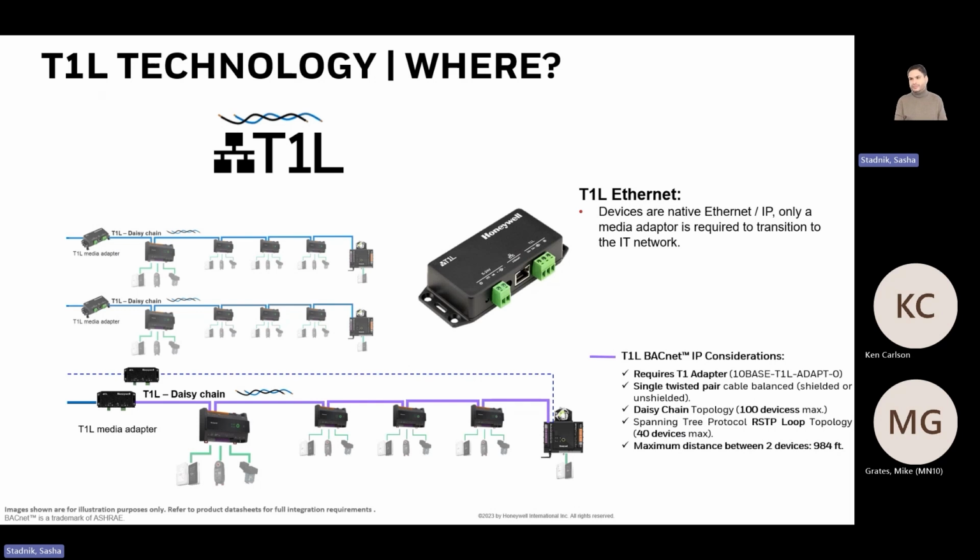Loss of power and loss of communication. So how the Ethernet standard works: when the IEEE designed the T1L standard, every single manufacturer of the T1L chip has to follow that standard. The standard specifies that the chip needs to communicate that there has been a communication loss on the chip.